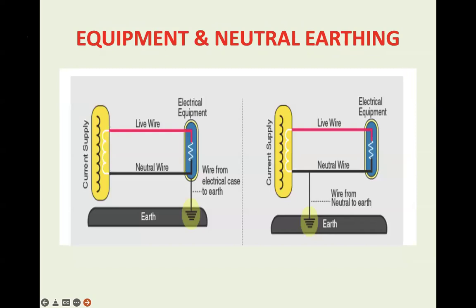I have talked about the important role of earthing and grounding. It is important to mention here that every fault current will be going back to the source. If you provide a dedicated low resistance path, you help the protective device to operate. If you are not providing that system, one thing is bound to happen. There will be an arcing ground or there will be a shock position.